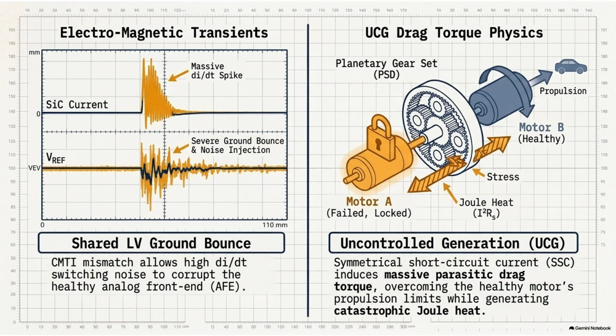And once that enamel melts, the high-voltage energy inside the dead motor can arc across parasitic capacitance, finding a path. It shoots high-voltage spikes back up the line, bypassing all those initial protections, and literally burns out the low-voltage control board anyway. So the mechanical drag creates a thermal runaway that loops back and destroys the electronic brain. The physical failure infects the software. It's like a horror movie for engineers.